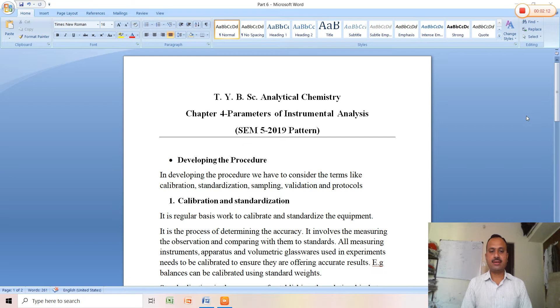All measuring instruments, apparatus, and volumetric glassware used in an experiment need to be calibrated to ensure they are offering accurate results. So, before starting the experiment, it is needful to carry out the calibration of the instrument, apparatus, and volumetric glassware with good accuracy. For example, balances can be calibrated using standard weights. All analytical balances can be calibrated using standard weights. Now, these weights are universally accepted.